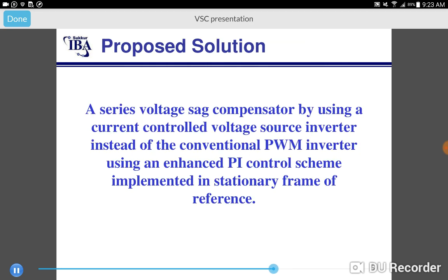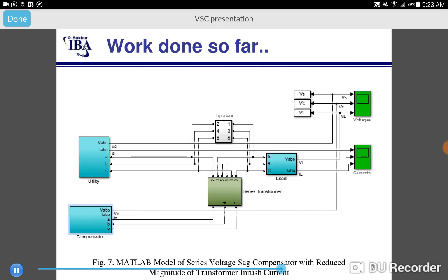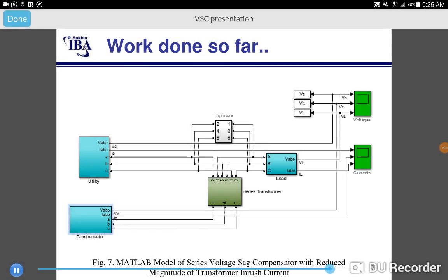Due to this reason, this research proposes a series voltage sag compensator by using a current-controlled voltage source inverter instead of the conventional PWM inverter, using an enhanced PI control scheme implemented in a stationary frame of reference. Here's the MATLAB Simulink model for series voltage compensator. The earlier discussed simple block diagram has been implemented here. Simulink model diagram of a series voltage sag compensator is illustrated here. It consists of a compensator to generate the compensated magnitude to the load voltage, a series transformer to add up the compensated voltage to the grid line, and the thyristor switches to bypass the series transformer for the period of regular grid operation.